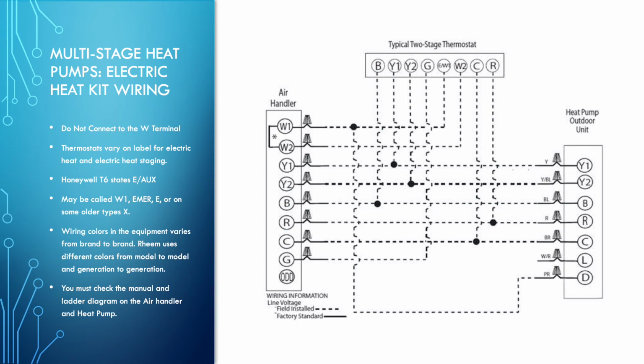We don't necessarily have to have the thermostat controlling the various sequencers, and most often we do not. Usually there's not enough wires anyhow, but more commonly we just allow the air handler and how we do our wiring setup to control that. The labels on the thermostat, that is ranged and varied. So on the Honeywell T6 thermostat, you'll see an E with an AUX. Now this schematic diagram that came out of the Rheem manual is showing EW1, and then it shows a W2.